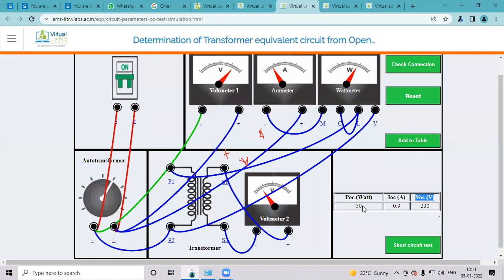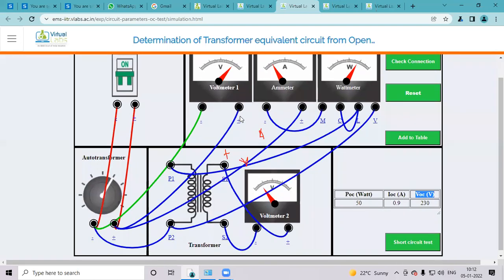All of you take this no load reading, take a screenshot if you want. Only one reading is required for the calculation, same for short circuit and open circuit test. So no load power taken from the supply is 50 watt, no load current during open circuit test is 0.9 ampere, and the supply voltage applied during the no load test is 230 volt. This is the open circuit test reading, now we want to do the calculation, after which we will conduct the short circuit test.